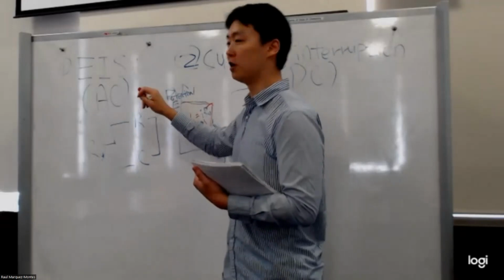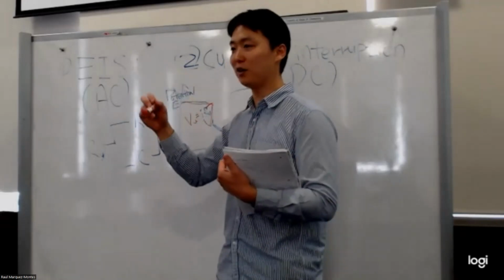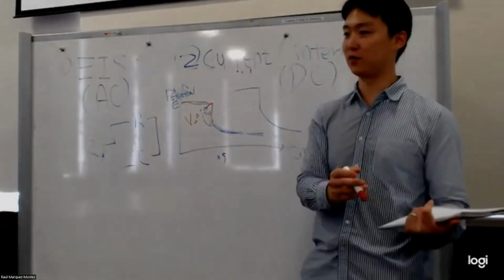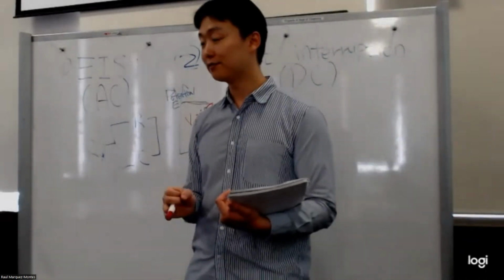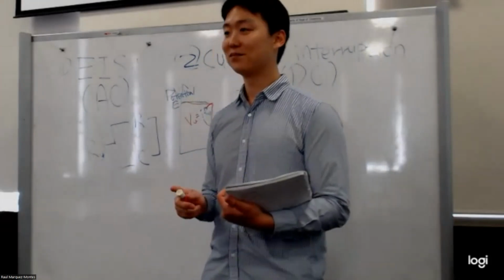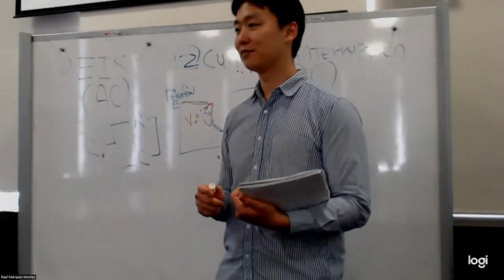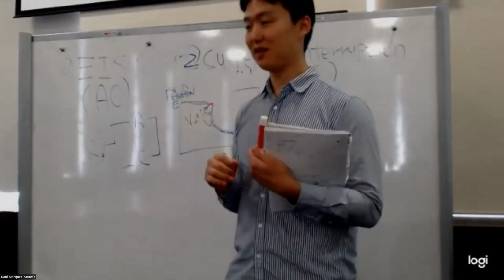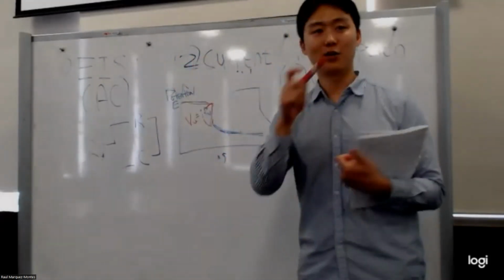So that's when we do the impedance analysis first, obtain the RU value, and do the IR compensation for the actual electrochemical analysis, like cyclic voltammetry. When you plug that into your potentiostat, it pops up with what your experiment is, and then at the bottom there's uncompensated resistance, and you plug in that specific value for that setup. Yes. Okay. Yes, go ahead.